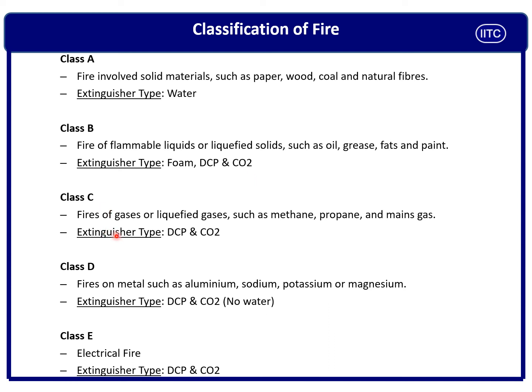Class C fire involves gaseous or liquid gas fuels such as methane and propane. To extinguish Class C fire, we displace oxygen using heavier gases — CO2 and DCP are heavier than air, so they displace oxygen. This creates starvation, removing oxygen from the fire triangle to extinguish the fire.